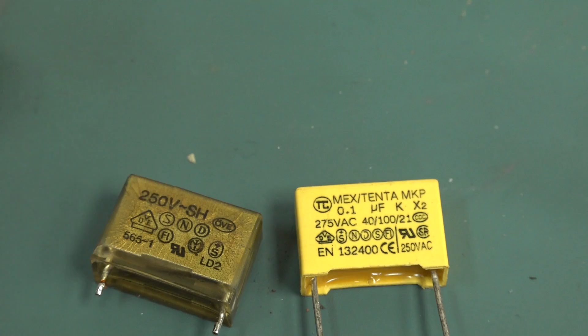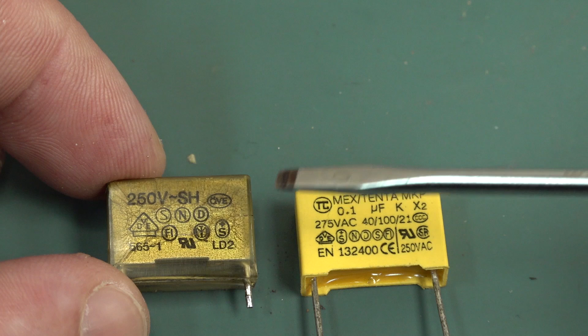These older ones do, unfortunately, degrade over time, but they're supposed to not do that. Whereas your Y-class caps are designed to go from active or neutral down to ground, and they're designed not to have any leakage at all down to ground. So they're designed for different purposes.